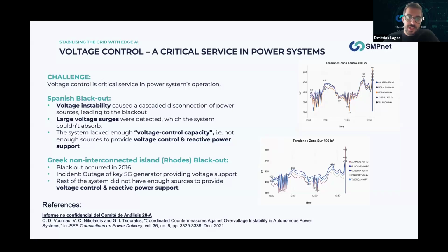Of course, this is not a new incident. In Greece, we had a similar incident also on a Greek non-interconnected island, Rhodes, where a blackout occurred in 2016. The incident there was that the key synchronous generator that was mainly providing the reactive power support and voltage control was disconnected, leaving the rest of the resources with insufficient voltage control and reactive power support capabilities, which led again to high voltage values, disconnection of distributed generation, and eventually blackout in the system.